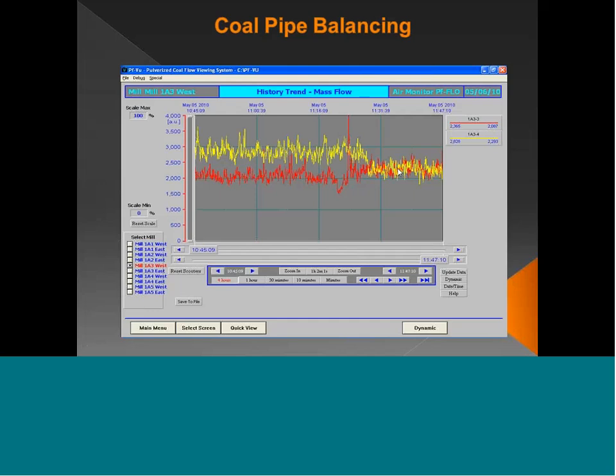Now, how much is it going to decrease or increase? Well, it depends on how much less work it has to do, because there's less mass of coal in the pipe. So often there's not much of a velocity change, but if the milling system continues to deliver coal to the heavy pipe and you continue to close your valve, you will create low velocities. So care has to be taken to look at both the mass flow and the speed.